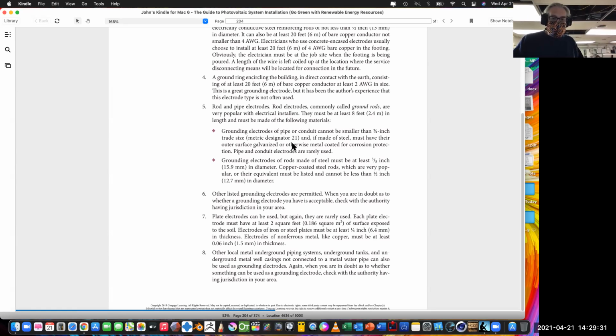We already determined that. We know what it needs to be. We said 5/8 number 8. We already did all that. Now we're beating it into the ground. And now we've got some of these other things that say each plate electrode must have at least 2 square feet of surface exposed to the soil. Electrodes of iron or steel plates must be at least 1/4 inch in thickness. Just beat it in the ground.